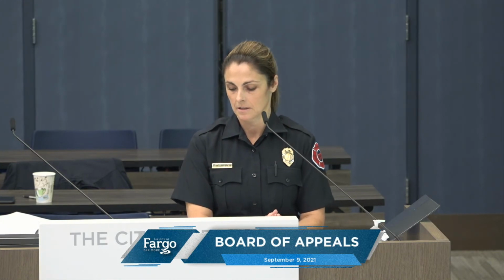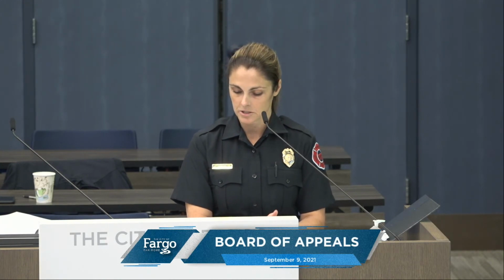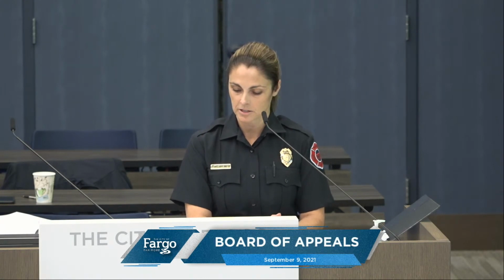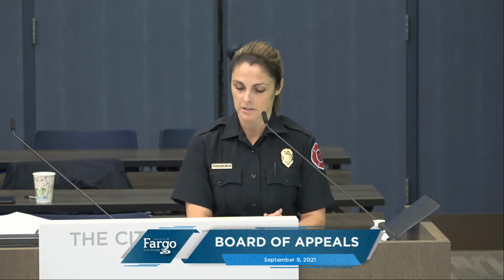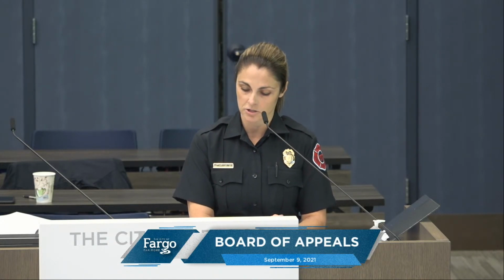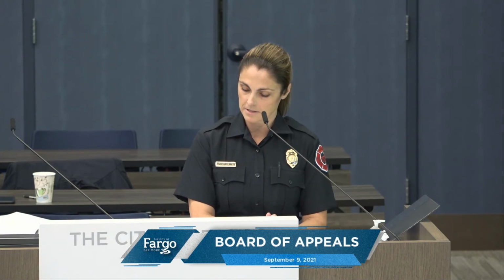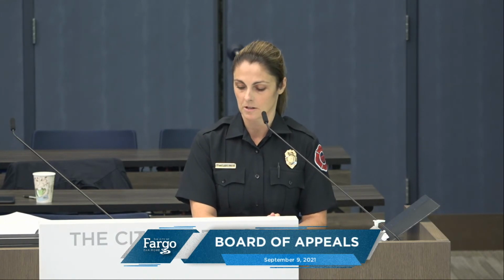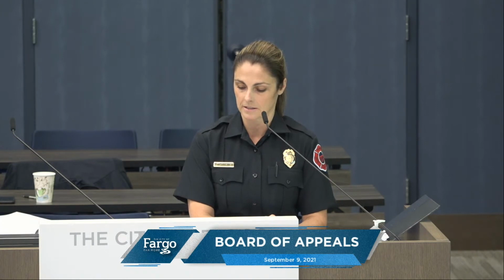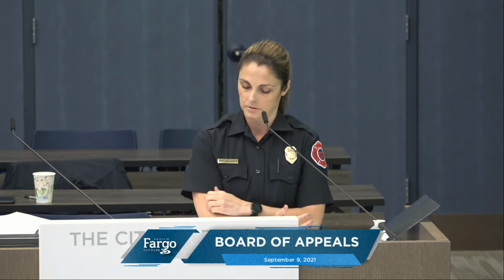Page 10-10, section 1008, means of egress illumination. Illumination level under normal power, which is section 1008.2.1. This section is modified and additional requirements specifically regarding exits is addressed. This illumination level at 10-foot candles at the walking surface along exit stairways, and at the required landings when the stairway is in use.